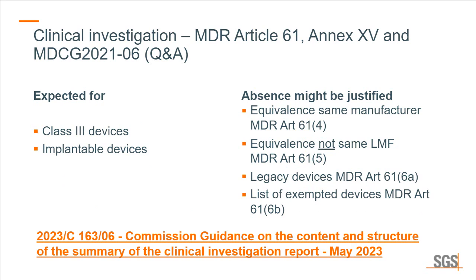When we talk about clinical investigation, and this is outlined in the MDR Article 61, Annex 15, and the MDCG 2021-06 guidelines. So clinical investigation is expected for Class 3 devices and implantable devices by default, unless you can justify why they are not needed. But, realistically, for a notified body, you will have a very hard time justifying these.